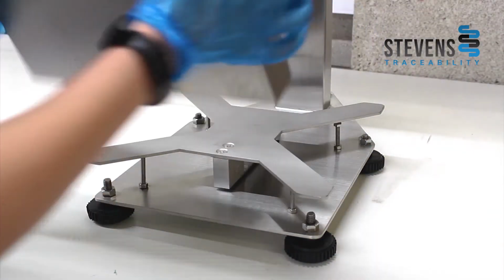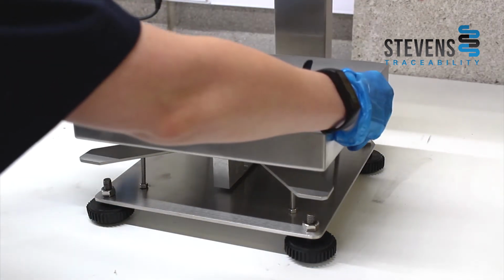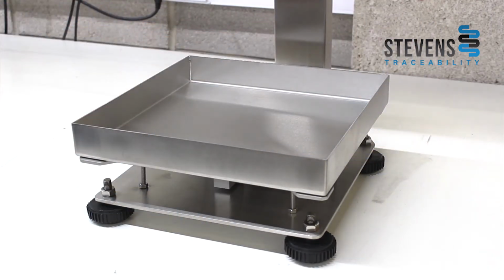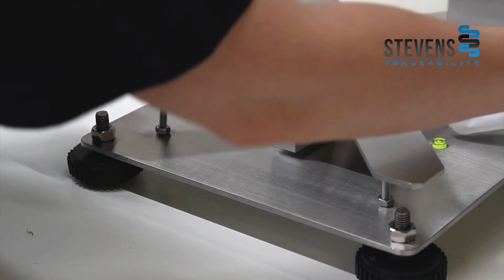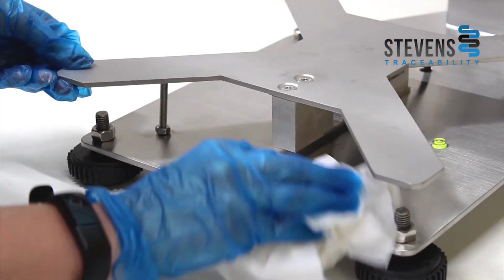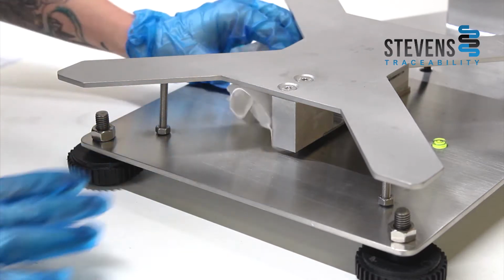Checking that when you jet wash it, you only jet wash the base and not into the junction box, as this can fill it up with water and cause weighing issues. You want to check there's no build up of muck underneath the plates or underneath the scale, which could stop it weighing correctly. Simple things building up underneath will stop it weighing correctly in each corner or underneath the load cell. You want to check the load cell isn't covered in any muck or debris, and you want to make sure the cables aren't covered in muck or debris, as this can also cause weighing issues.